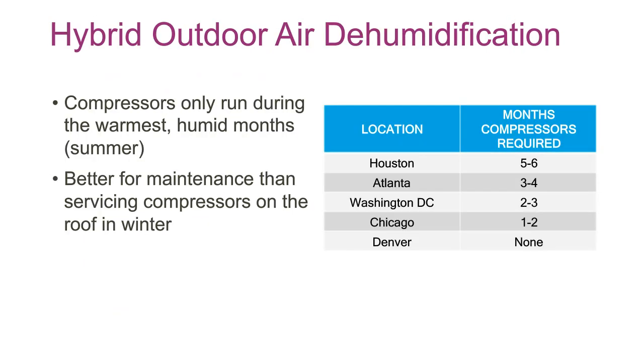So when you use this hybrid idea, your compressors are only running in the warmest, most humid months. I've got a few locations here showing how much compressor operation you need. In Chicago, it's really only 1 to 2 months of the year, 3 to 4 in Atlanta. You can see DC. In an arid, mountainous climate like Denver, 50% fresh air will dehumidify to the design dew point day out there. So you don't even need to use it for anything other than space cooling.